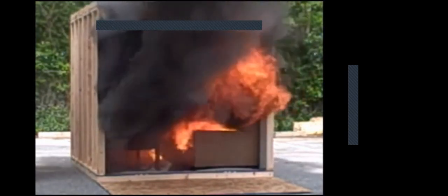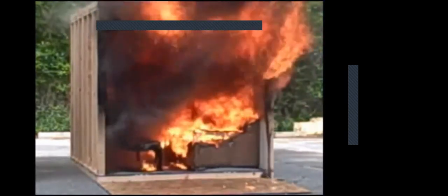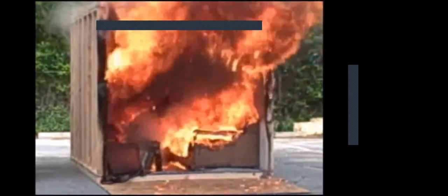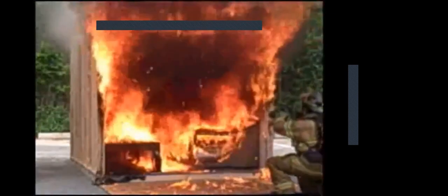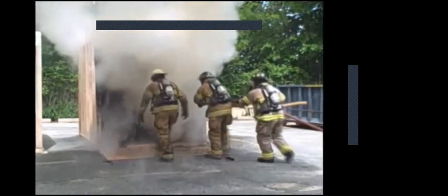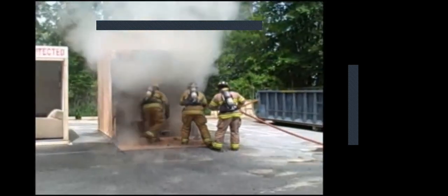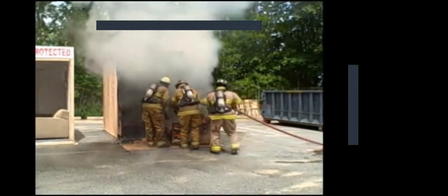All right, in a moment, if you look at the newspaper on the floor, when that ignites, that's about when flashover will occur, which is just about now. Okay, now we are at full flashover. The room is fully engulfed, and the firefighters are going in to extinguish. Now, folks, the total elapsed time on that, from the ignition to the time we began putting the fire out, was 1 minute and 30 seconds. So when people say you don't have much time to get out of a burning house, now you can see why.